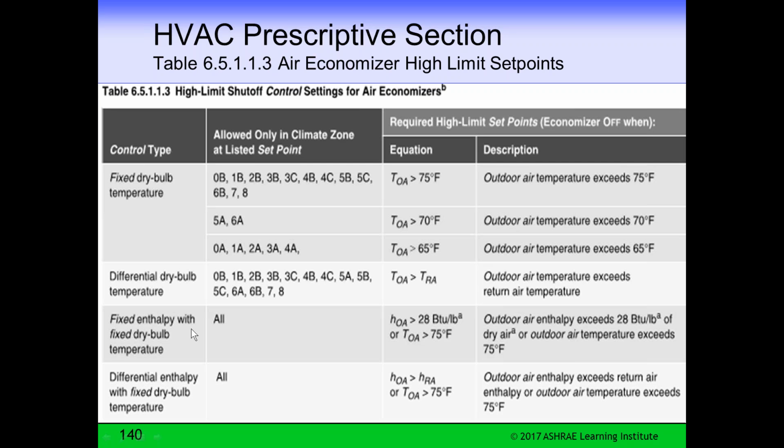You can buy a very expensive one for the total building and maybe use it, and it'll work out for you. But that's why we've added this dry bulb temperature, because we agree that dry bulb is more reliable. If we want to use the economizers, the controls have to work, and if the enthalpy sensor's not working, then we're not going to save the energy we intended to.